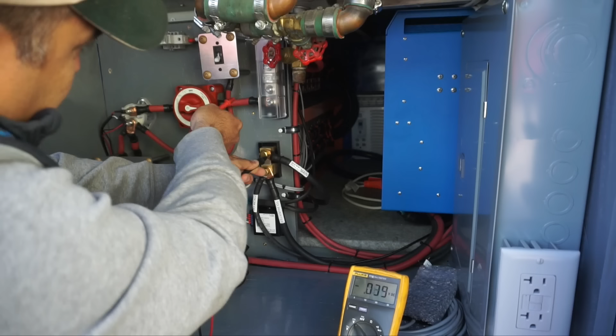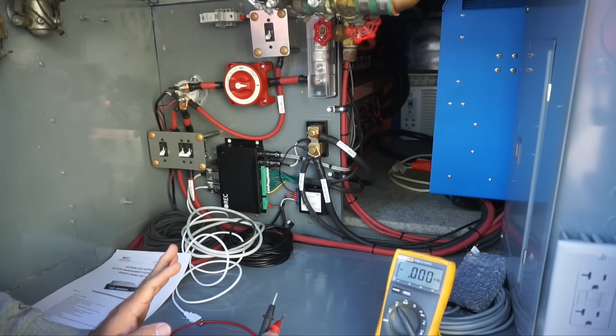On this one, we shouldn't see anything, because this contactor works as a giant on and off switch for the BMS to turn power off if it finds problems. So now these wires go to each of the cells. If we go to ground and then to the power wire, we should also see 55.6 volts.